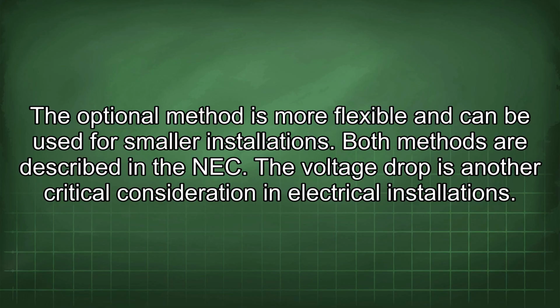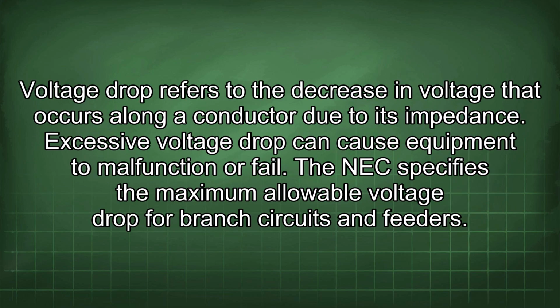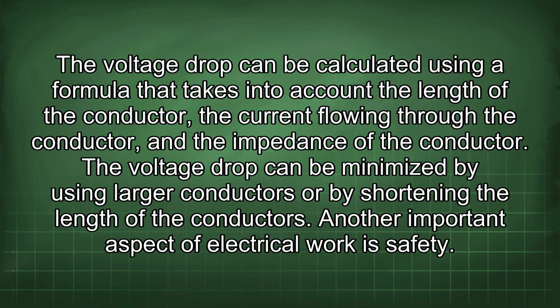The voltage drop is another critical consideration in electrical installations. Voltage drop refers to the decrease in voltage that occurs along a conductor due to its impedance. Excessive voltage drop can cause equipment to malfunction or fail. The NEC specifies the maximum allowable voltage drop for branch circuits and feeders. The voltage drop can be calculated using a formula that takes into account the length of the conductor, the current flowing through the conductor, and the impedance of the conductor. The voltage drop can be minimized by using larger conductors or by shortening the length of the conductors.